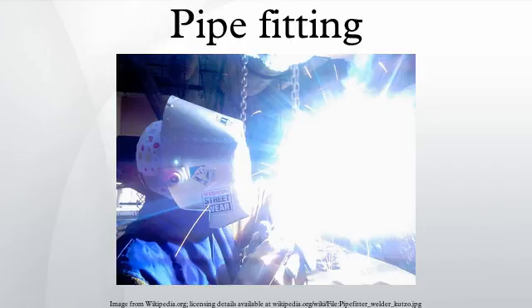Compression connections. Compression fittings use a soft metal or thermoplastic ring which is squeezed onto the pipe and into the fitting by a compression nut. The soft metal conforms to the surface of the tubing and the fitting, and creates a seal. Compression connections do not typically have the long life that sweat connections offer, but are advantageous in many cases because they are easy to make using basic tools. A disadvantage in compression connections is that they take longer to make than sweat, and sometimes require retightening over time to stop leaks.